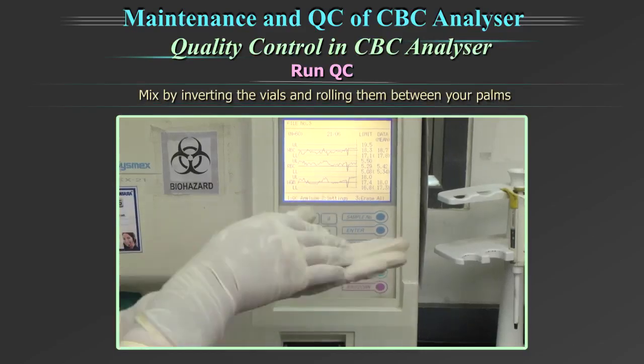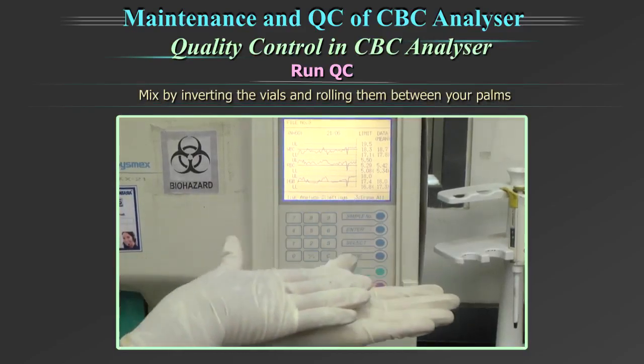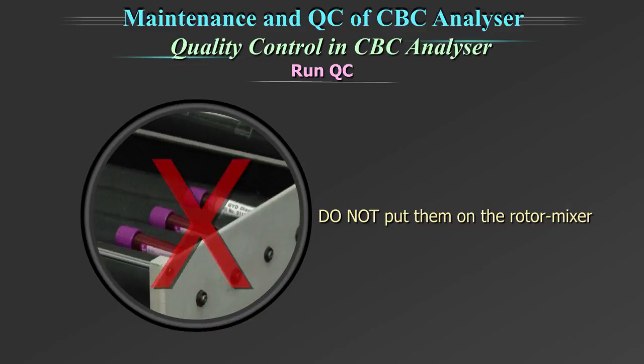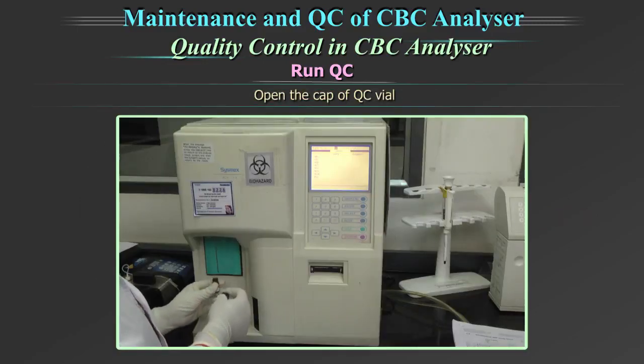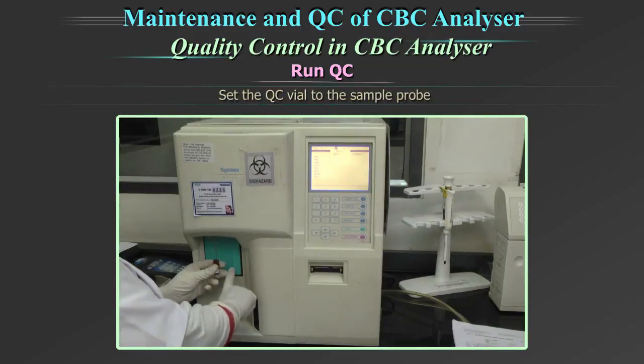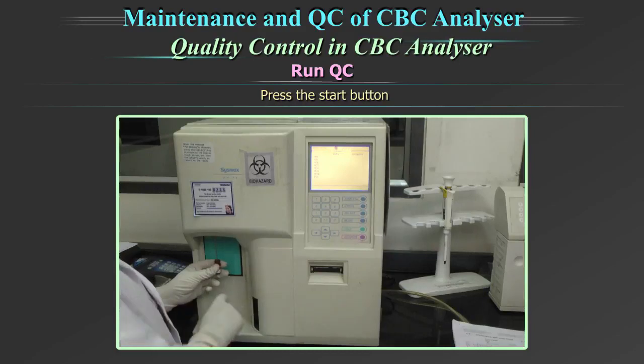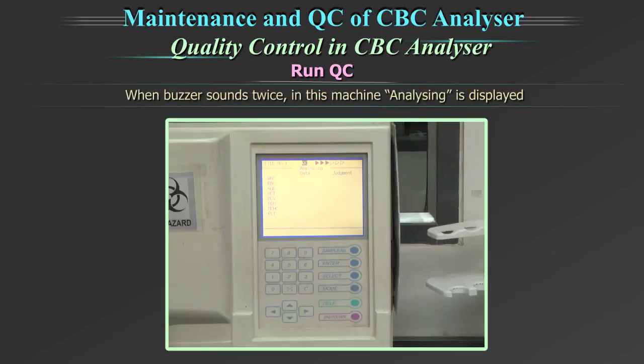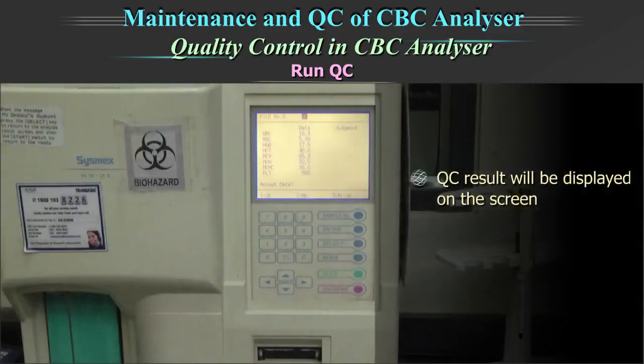Mix by inverting the vials and rolling them between your palms. Do not put them on the rotor mixer. Open the cap of the quality control vial, set the QC vial to the sample probe and press the Start button. When the buzzer sounds twice in this machine, analyzing is displayed on the control analysis screen. You can remove the QC vial. The QC result will be displayed on the screen.